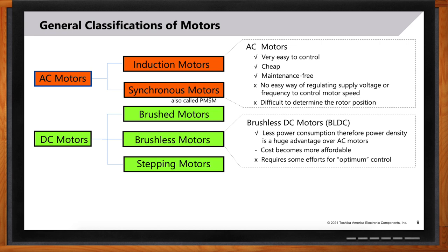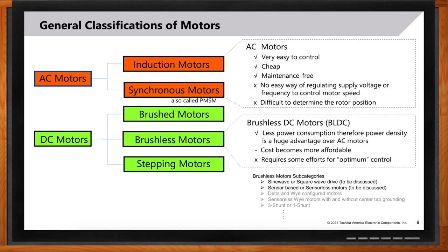Motors to which direct current is applied are called DC motors, which include brushed, brushless, and stepping motors. Both brushed and brushless motors can be used in similar applications, with cost and performance requirements determining the final choice. Brushless DC motors have less power consumption than AC motors, so their form factor can be smaller while having equivalent power density — a huge advantage. The cost is also coming down to an affordable level, with the only caveat being that controlling a brushless motor to its optimum requires some effort.